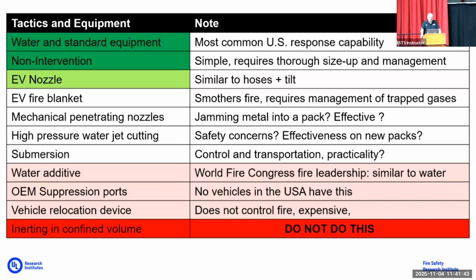High pressure water jet cutting - NFPA tested that, and I'll give you a link to their webinar. The timing is about the same as using the hose stream. The unit itself was very effective; I believe they only used 300 gallons of water through the unit. However, for safety they also had other hose lines operating for 20 minutes or more. So the overall water usage really isn't reduced.